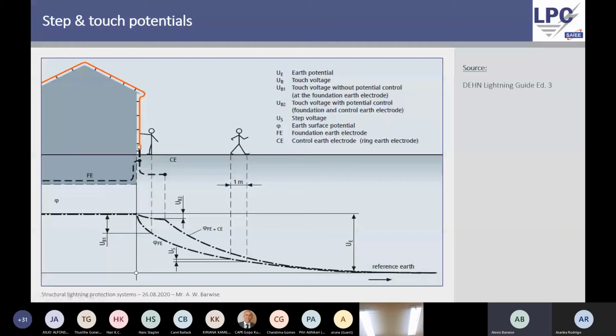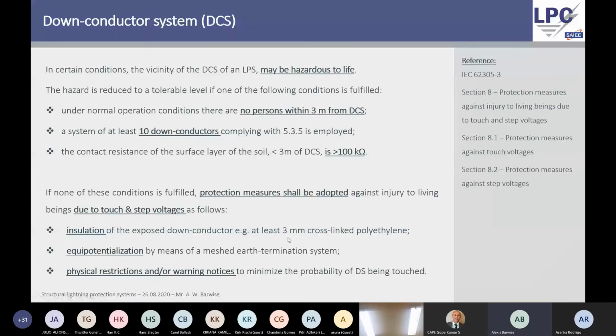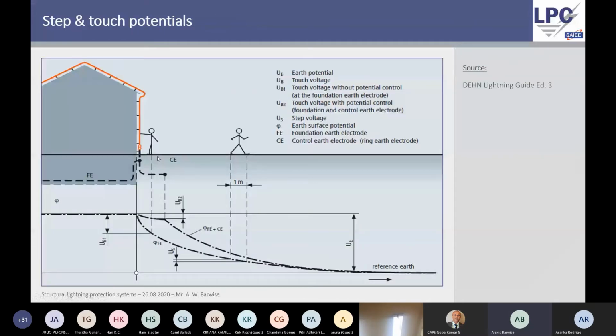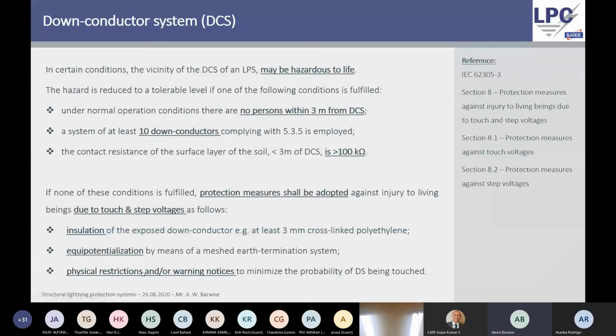And a very simple and pragmatic way is to use a conduit that's made out of PVC that's at least 3 millimeters thick, right? And place the down conductor inside this so that a human being cannot touch the conductor itself. We have to ensure, or we could use equipotentialization, right, between the earth termination system. So really here, build an earthing system underneath this human's feet such that there would be no potential difference. Or finally, we have to use physical restrictions, so almost barrier off an area, or place warning notices that people should not be in this vicinity during a lightning strike, or at least lightning conditions.